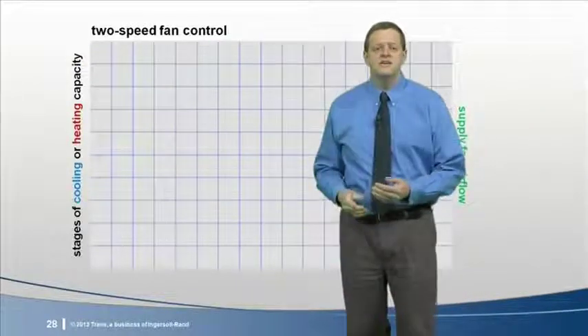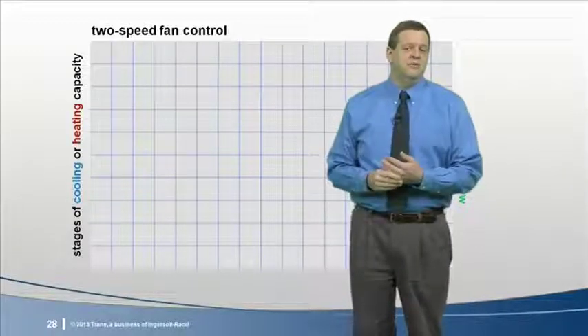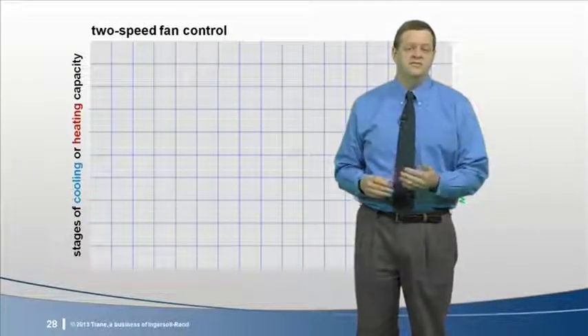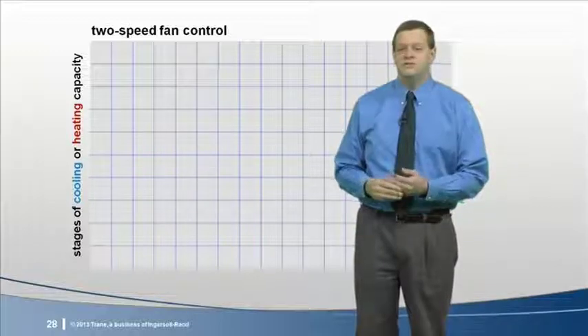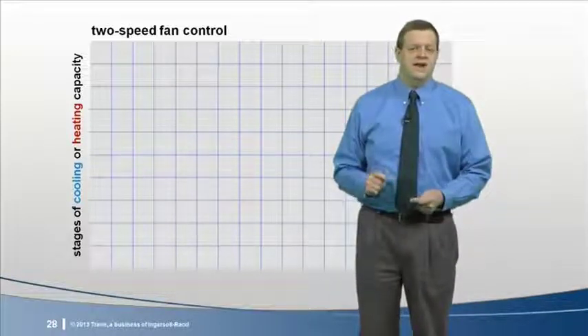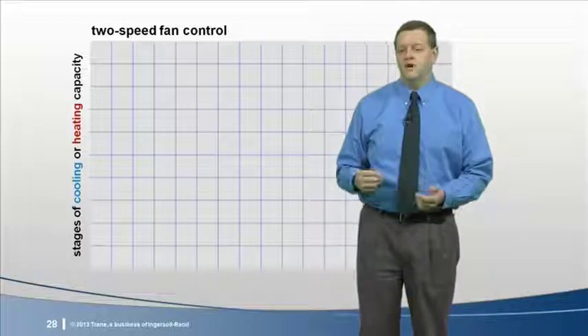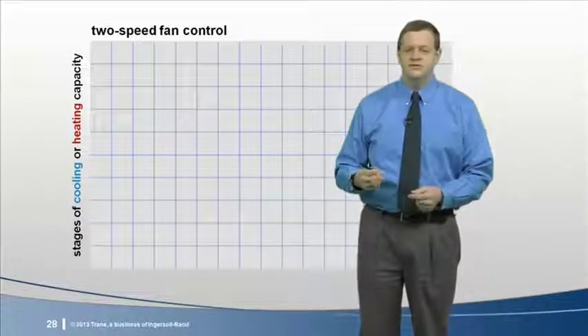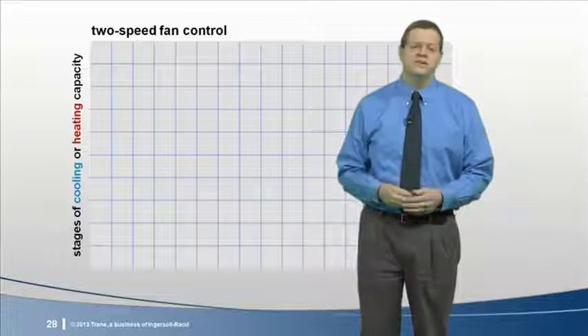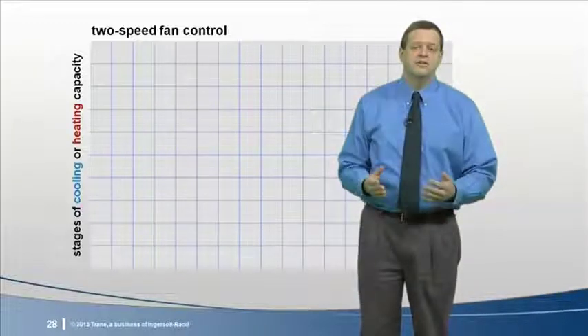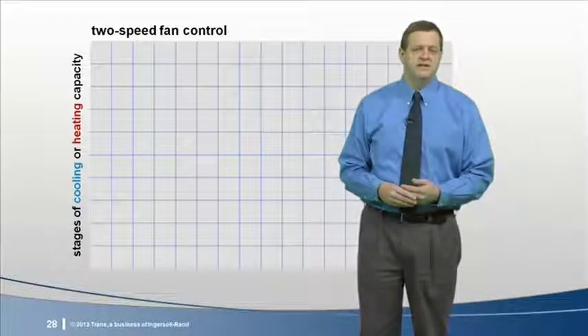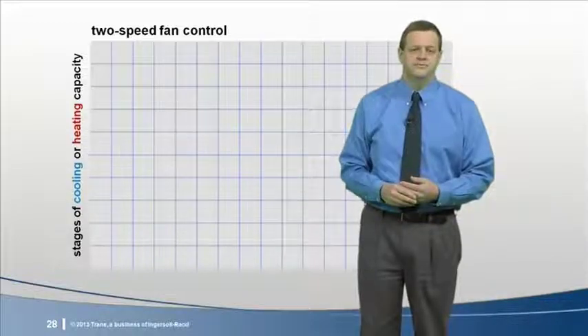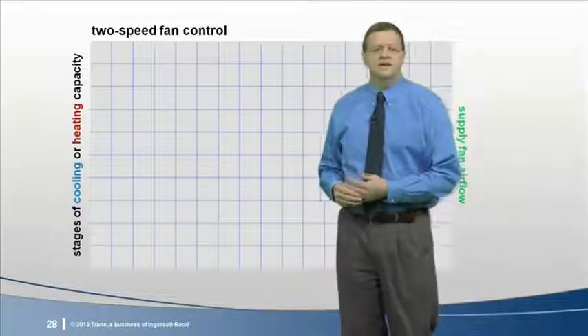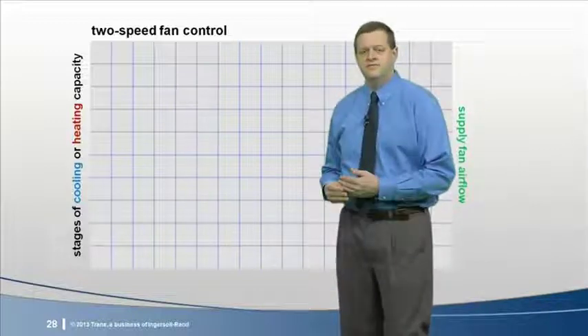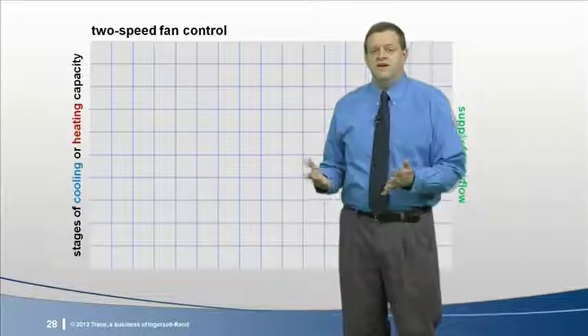In addition, as Eric mentioned, Standard 90.1 states that the supply fan can use either a variable speed or a two-speed motor. The most common implementation of a two-speed motor is probably a DX unit that has either two compressors or one two-stage compressor. This allows the equipment to be used with a conventional thermostat with Cool 1, Cool 2 control. This chart depicts an example control sequence when using a two-speed fan. Again, this can vary by manufacturer and product design, so this is just an example.